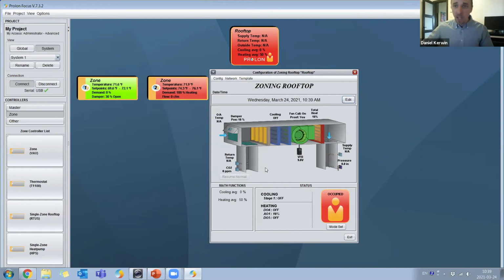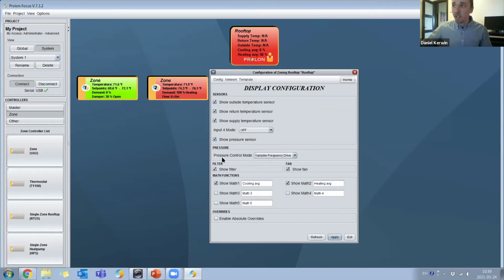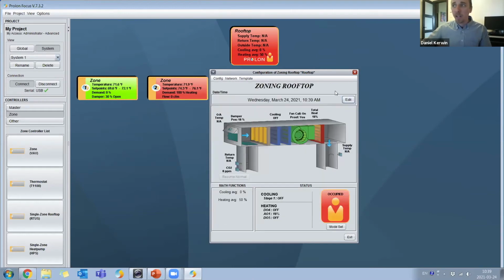Or in case we had another situation where it's just a constant volume unit, so there's no pressure control at all, I can just disable that entirely, just do config, edit display, pressure control mode will be none, and I do not want to see my pressure sensor right here. I'll just hit on the apply button, and when I go back, well, now we have the graphic for the constant volume units.